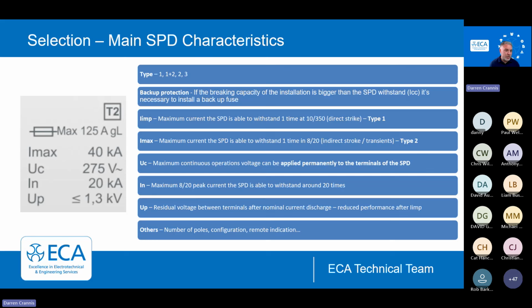Here we've got a type 2, but it could easily be a type 1 or a type 2 or 3. So straight away in that corner that says T2, that's the type of SPD. So we need to check that we've got the right one. In this case, it's a T2, that means type 2. It could be a T1 plus T2 or many variants of. So it's important we get the right device, especially if you've been asked to install a type 1 SPD and you get given a type 2. It's not going to work very well in that situation.